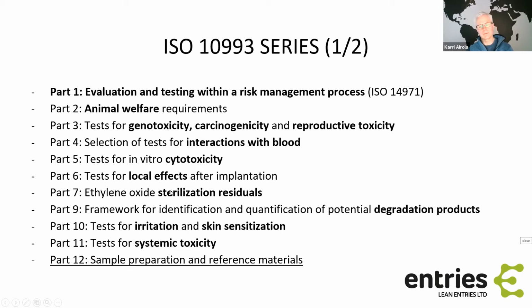There are nowadays a lot of good service providers with electron beam and gamma irradiated sterilization, which is a very good alternative to the ethylene oxide sterilization. But ethylene oxide has been a very standard, kind of not golden standard, but very much used. But it also can produce some residuals in the device. So you should do some biological testing and safety testing that you really don't have any ethylene oxide residues in the device.